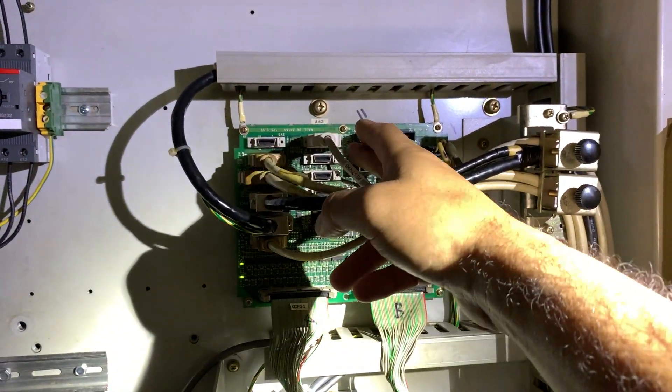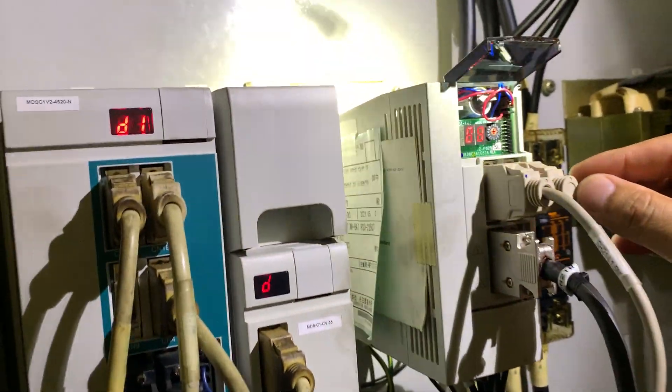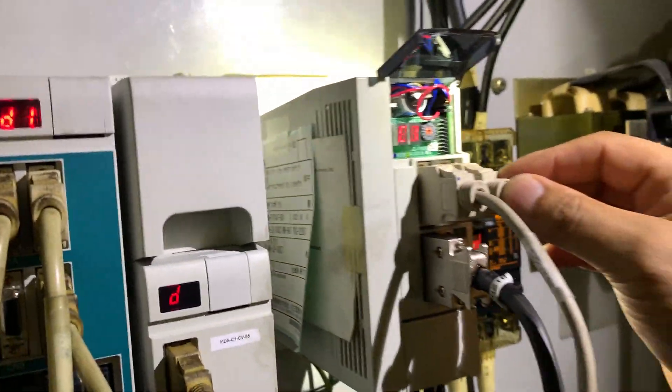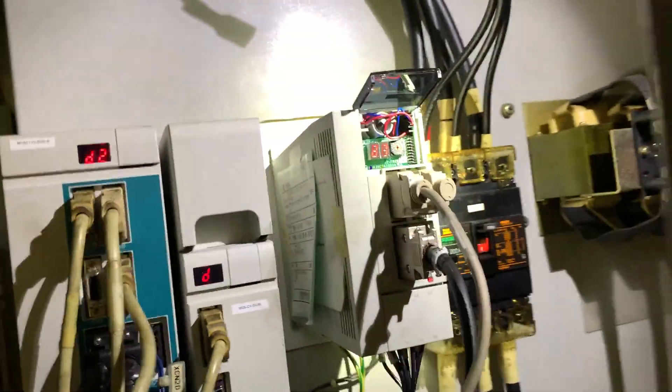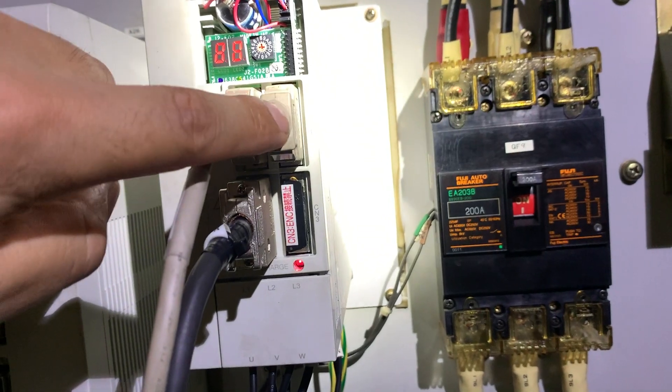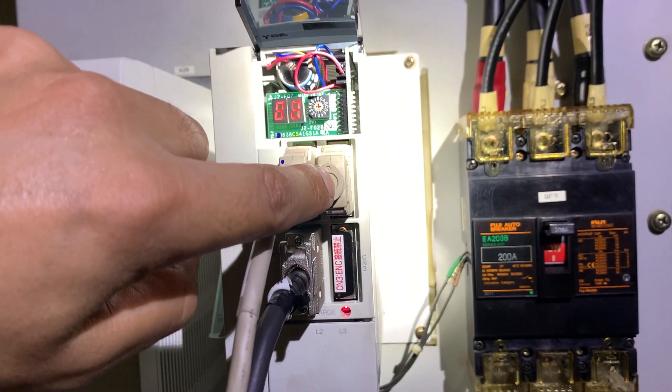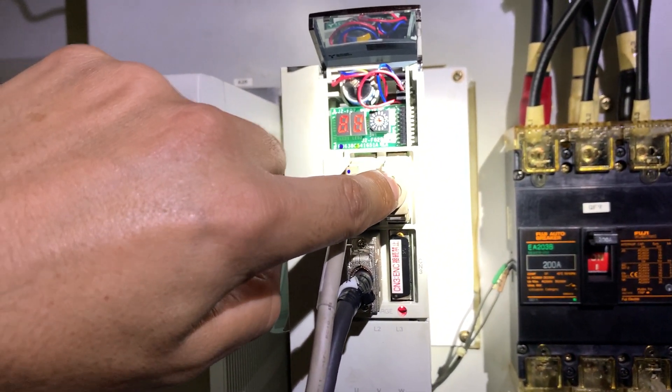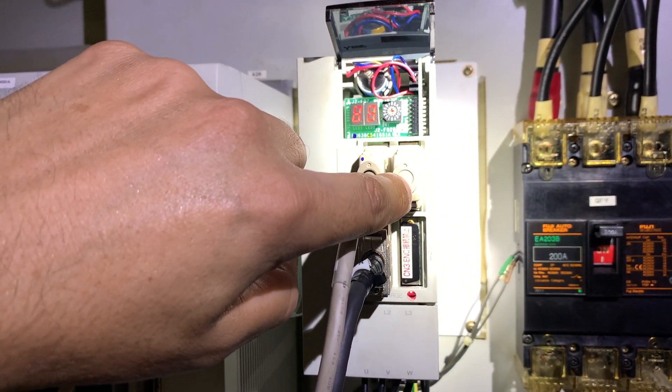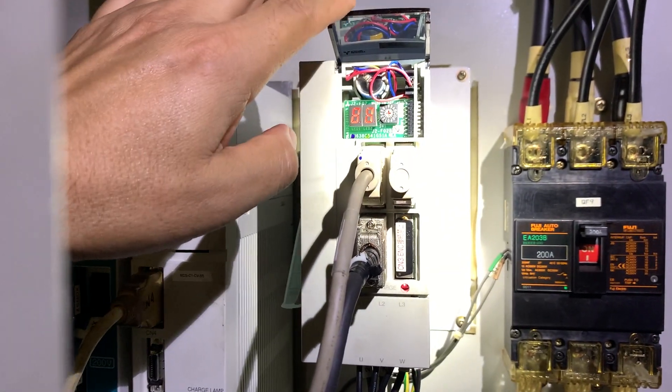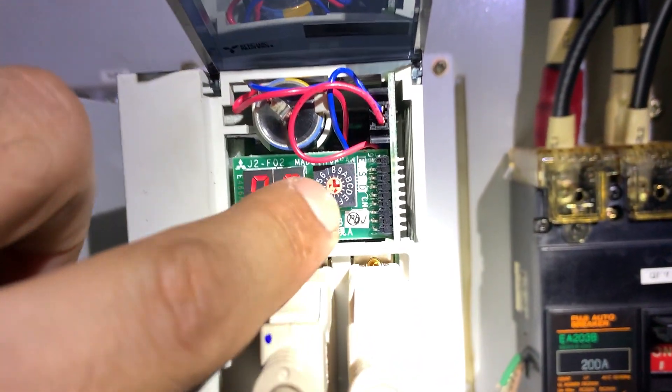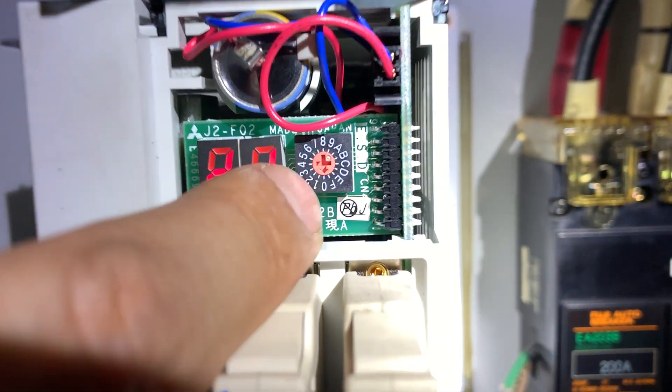It has a termination board through this port and it has a terminator which is to adapt the impedance and the address of the device on the communication line. The address of the drive is zero.